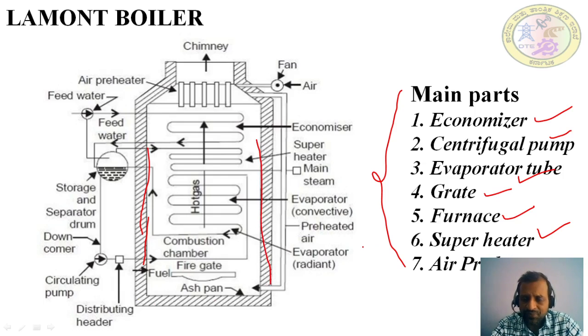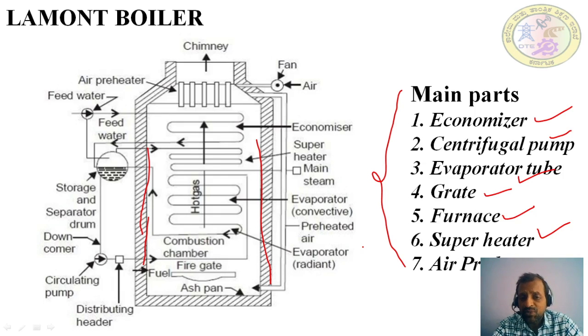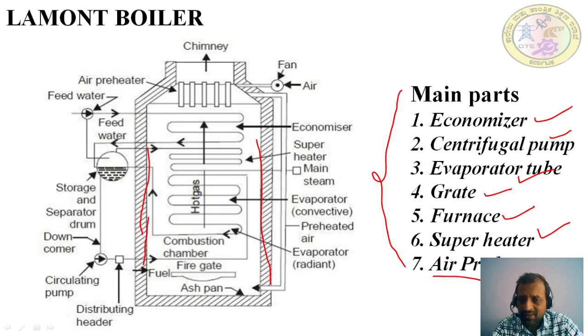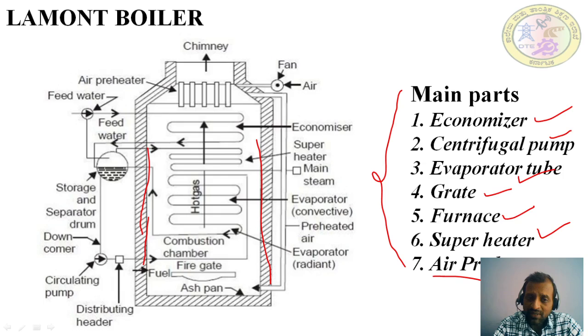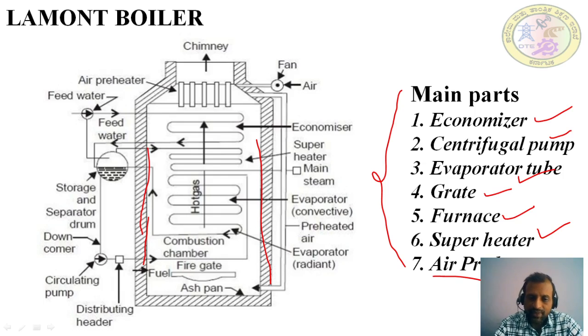The superheater is where dry saturated steam is sent and gets converted into superheated steam. The air preheater is an accessory that increases the efficiency of the boiler — as the name suggests, you heat the air before sending it to the furnace. The air is passed at the top near the chimney, and instead of using cold air directly from the atmosphere, you use heated air from the air preheater for the fire grate.